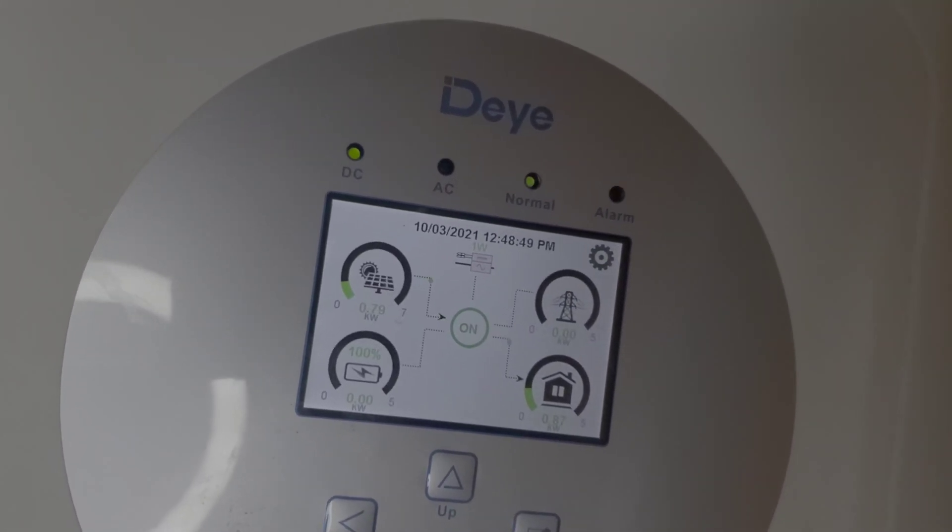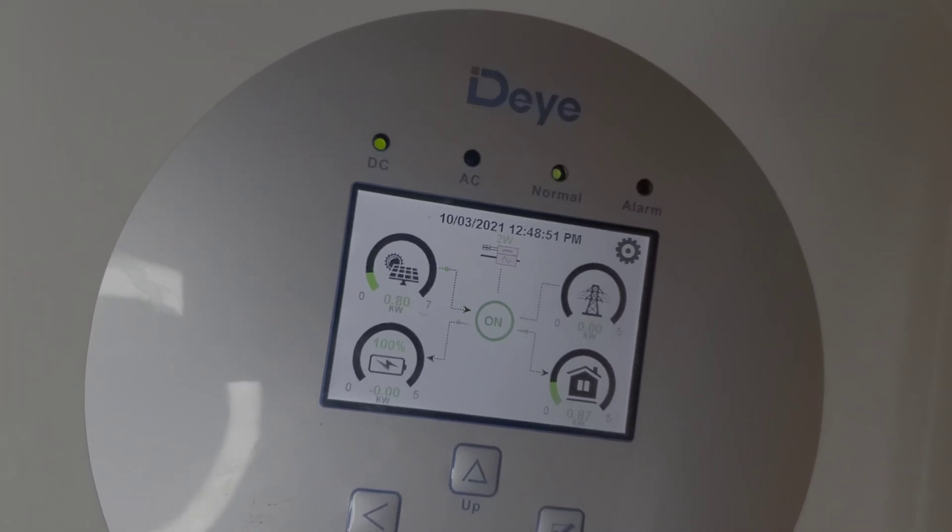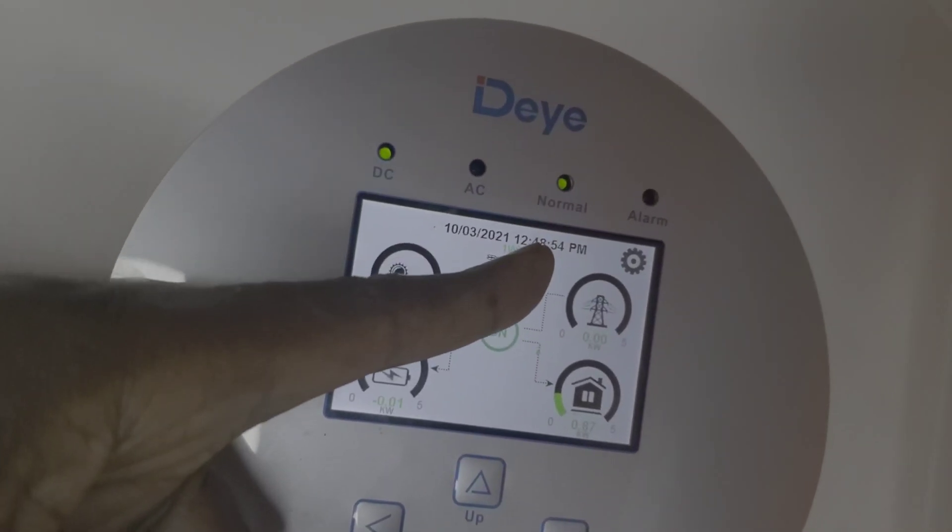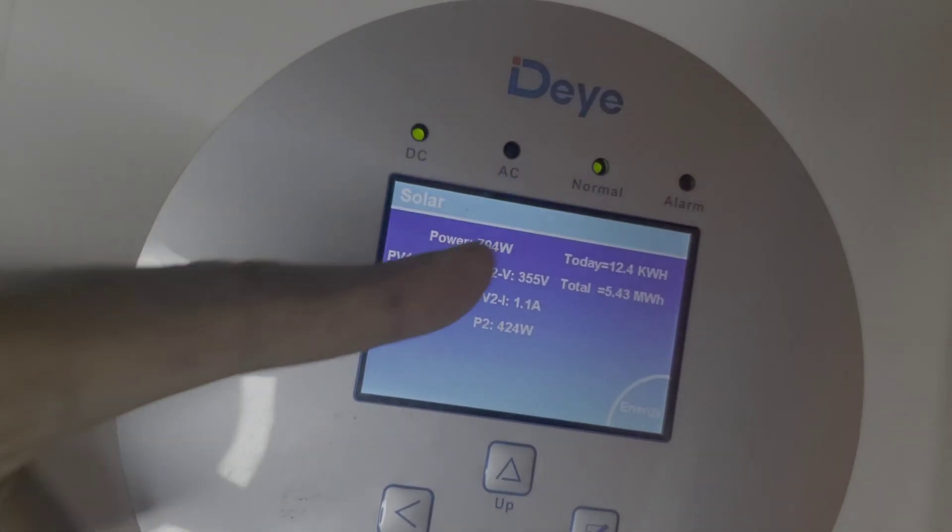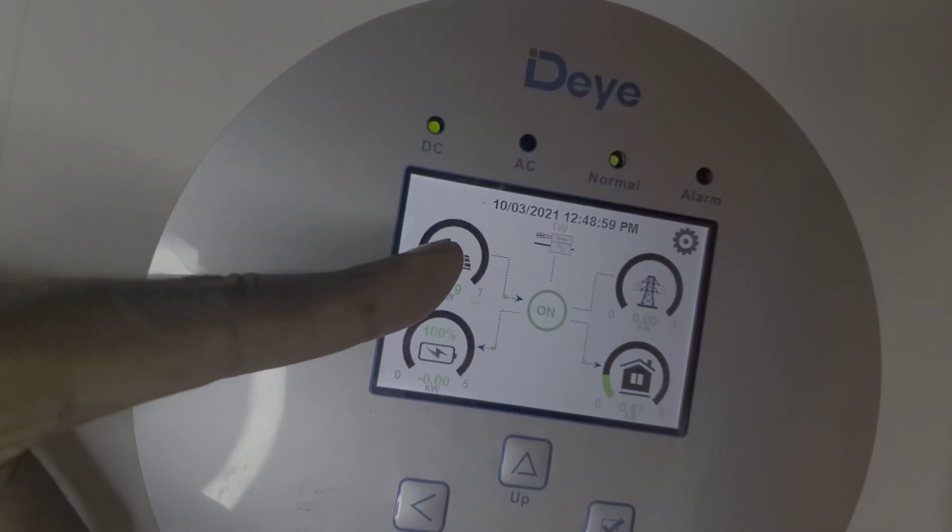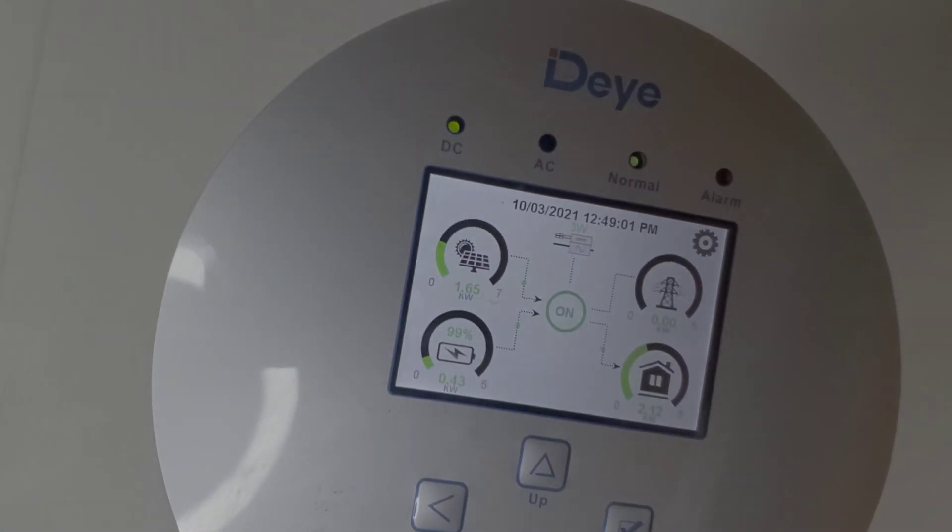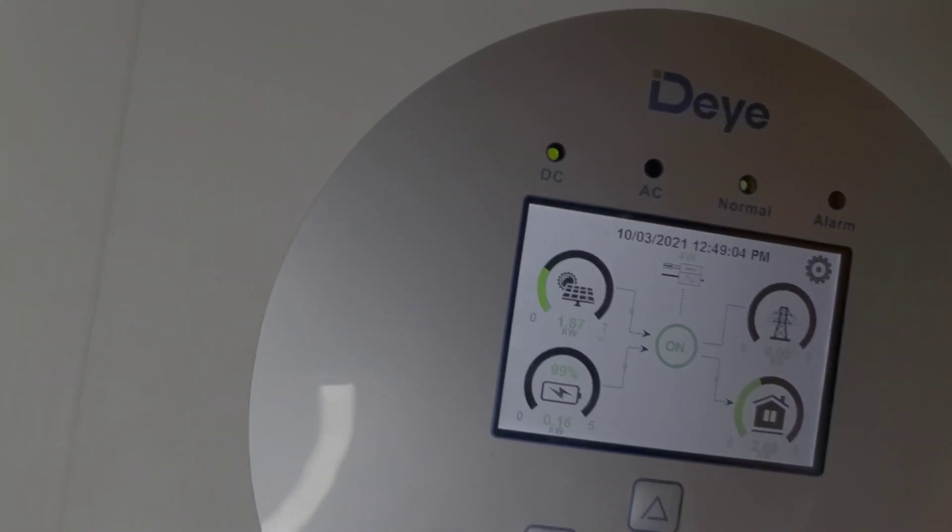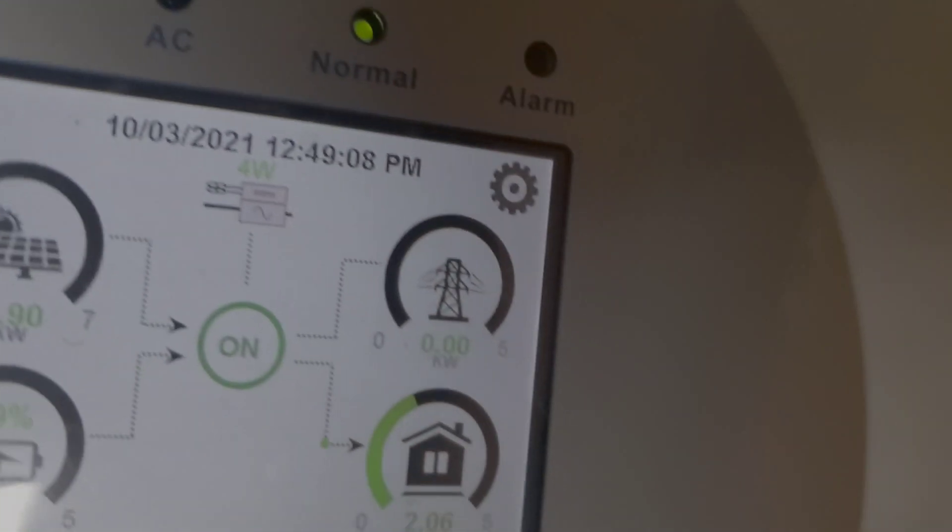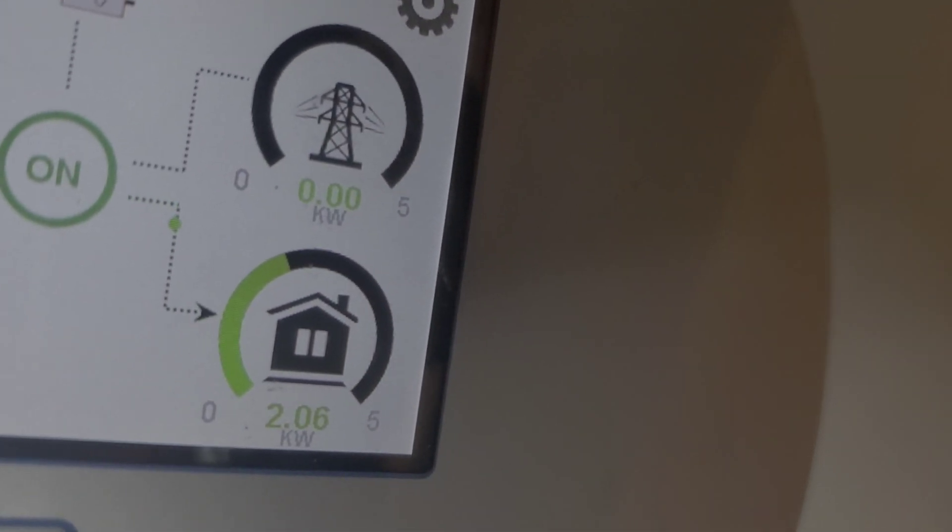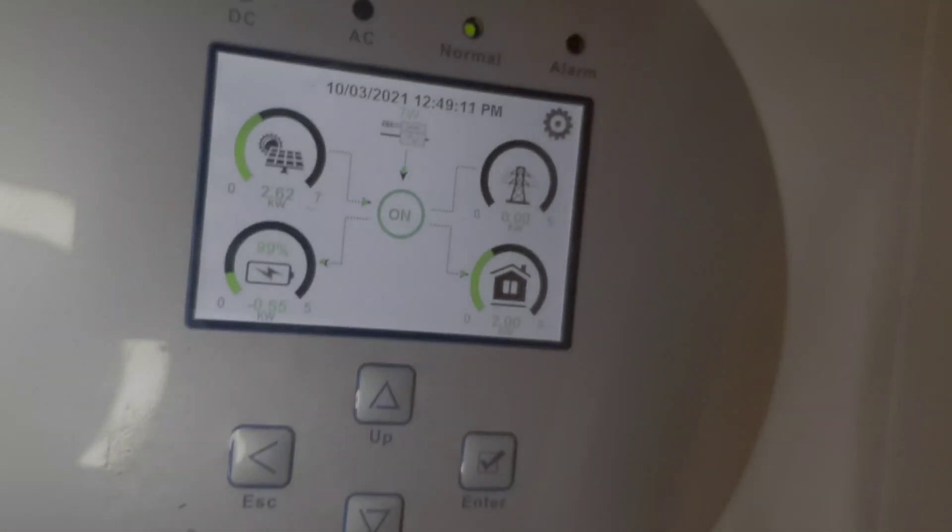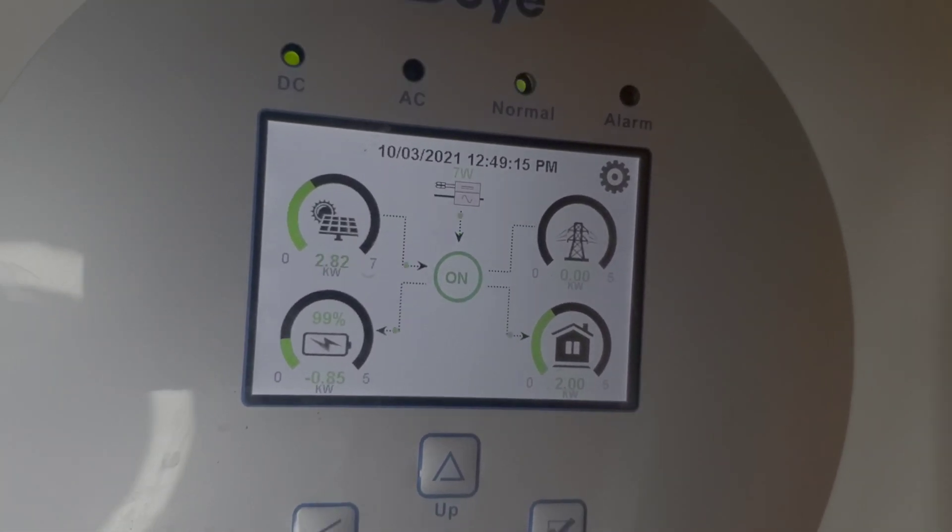So what will happen is, if it was producing 1,800 watts, 1,900 watts, once the BMS tells the inverter to reduce what it's doing, this can either go to zero or it will drop to match what is coming from the PV on the inverter side to match that 40 amps which is what the requirement is. As you see my PV production just spiked up because the microwave came on, and my consumption also went up. That's one thing it does.